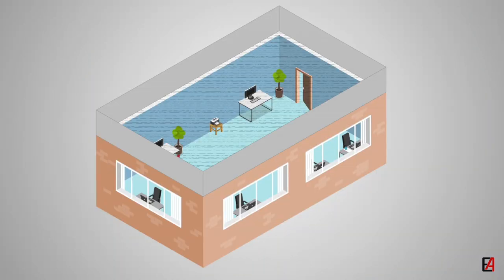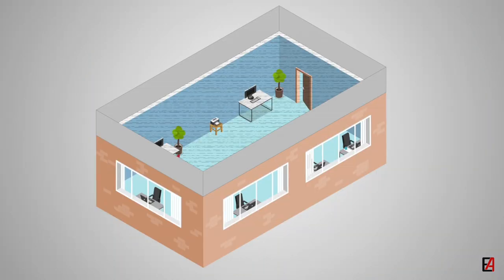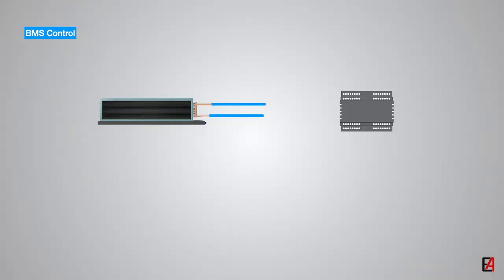Now we can discuss about the BMS sequence of operation for the fan coil unit. In this example, a room is being served by the FCU which is installed above the false ceiling with two discharge grills and three return grills on the ceiling. Fresh air supply and exhaust to the room is provided by an AHU. The main objective of this fan coil unit is to maintain the space temperature. To achieve this, a FCU controller is provided for each fan coil unit along with a space thermostat, which measures and feedbacks the space temperature constantly to the FCU controller.